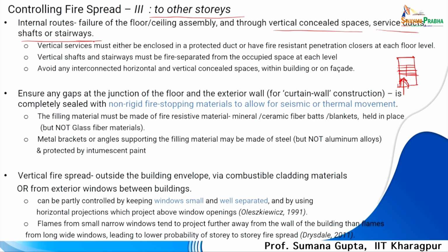So, this fire staircase has no smoke entering into this space. This door is the player controlling the smoke movement between the 2 stories, but in many cases we have open staircases. In that case the smoke, and if the staircase is just adjacent to the place of fire, even the fire, can move through this staircase.